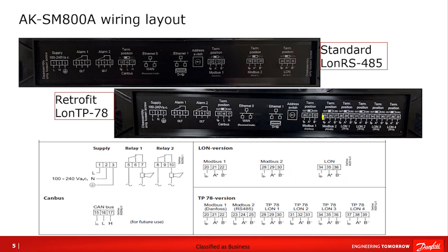For our retrofit version of the 800A, we have a specific part number for TP78 communication out of the System Manager. You'll see that we actually have four Echelon plugs here instead of just one. The rationale is these units are used for retrofit applications — older series controllers typically had multiple Echelon plugs, so this makes for a smoother transition of moving wiring over from the older System Managers to the newer.